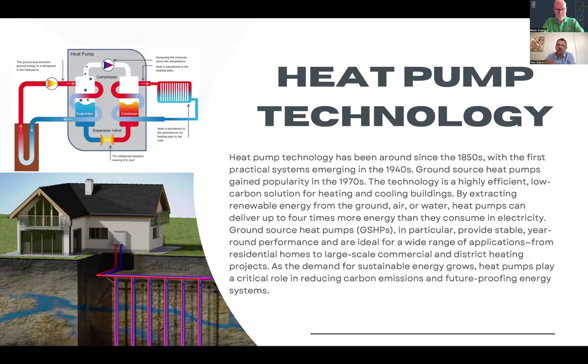Okay. So just a quick explanation of how heat pumps work, and they work in a similar way no matter if we're extracting water from the well, from the closed loop boreholes or from the river. We are taking the heat via the glycol from the boreholes and providing the heat to evaporator inside the heat pump, which you can see on the left-hand slide, on the top. And then the gas inside the compressor, the heart of the unit, is taking the heat away from the glycol.